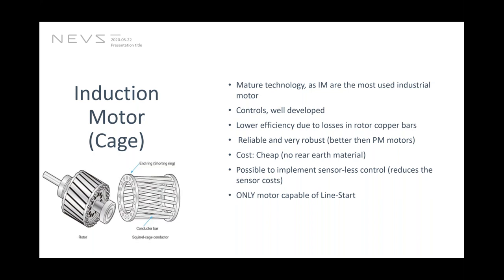With the induction motor, basically all the applications during the 60s, 70s, or even 80s and 90s had very limited controls. Almost all the applications used the three-phase induction motor, because they are line start motors. You can simply plug into a three-phase supply and it will run. You don't need any specific control for that. So whenever we are talking about the old system and comparing the efficiency, it will almost always be a comparison with the induction motors.